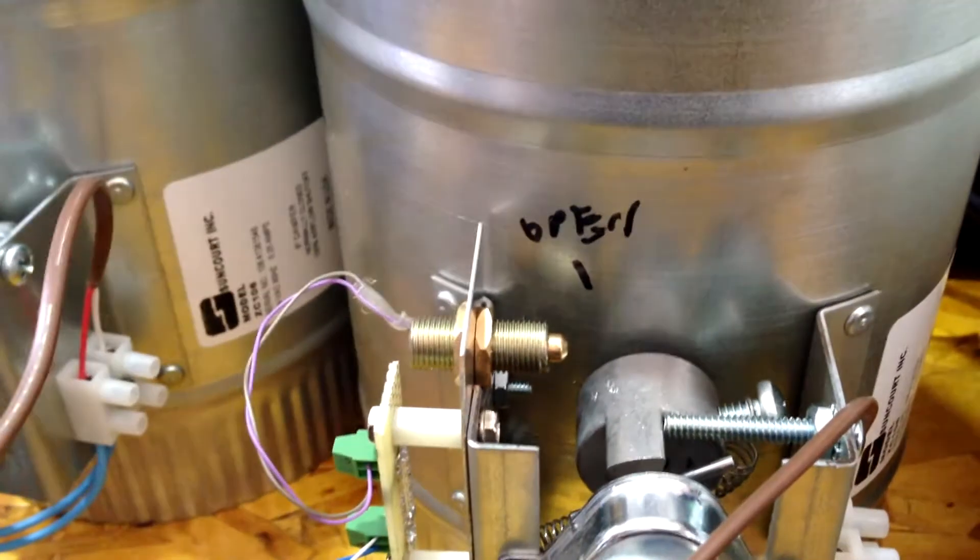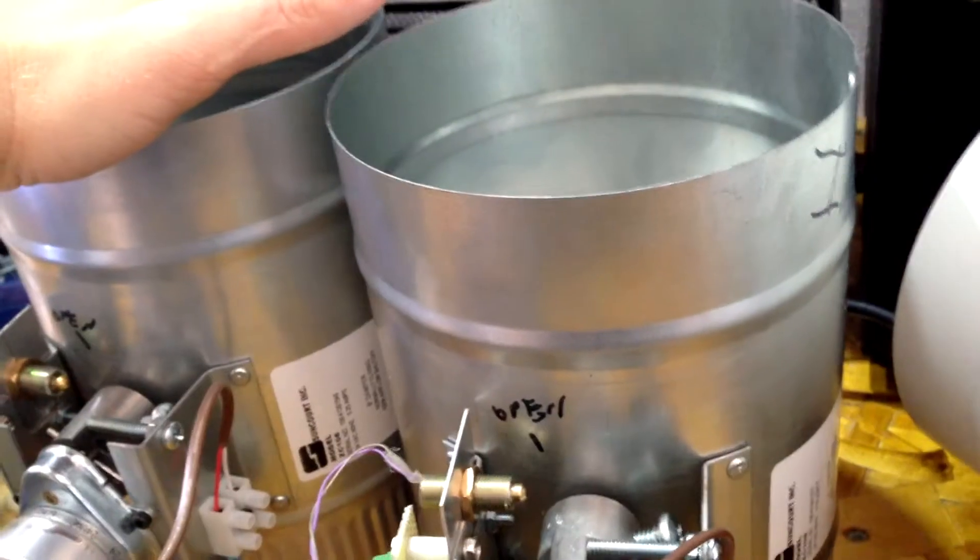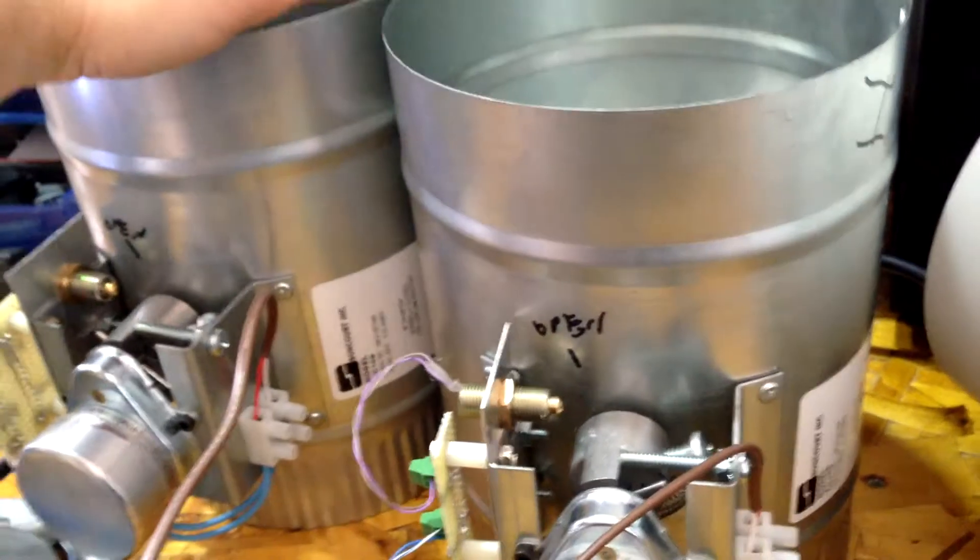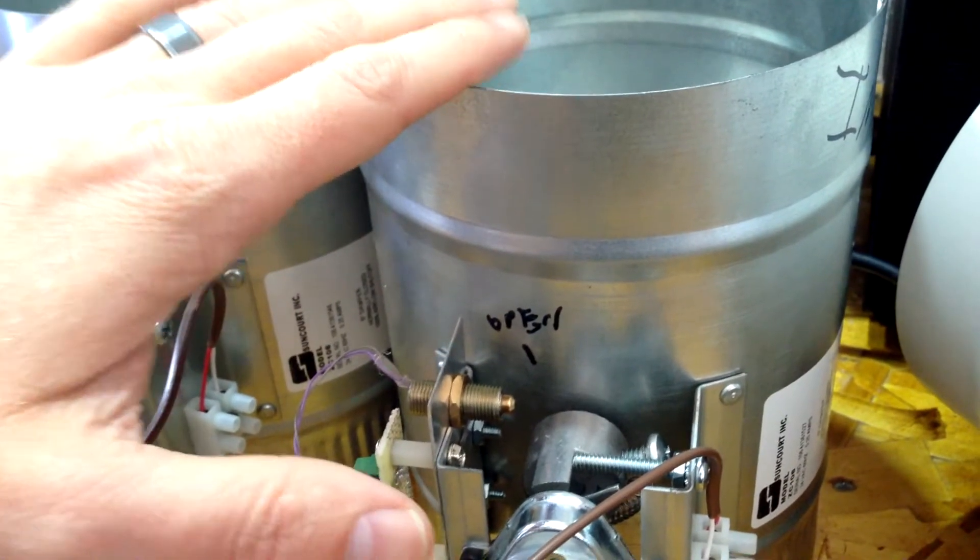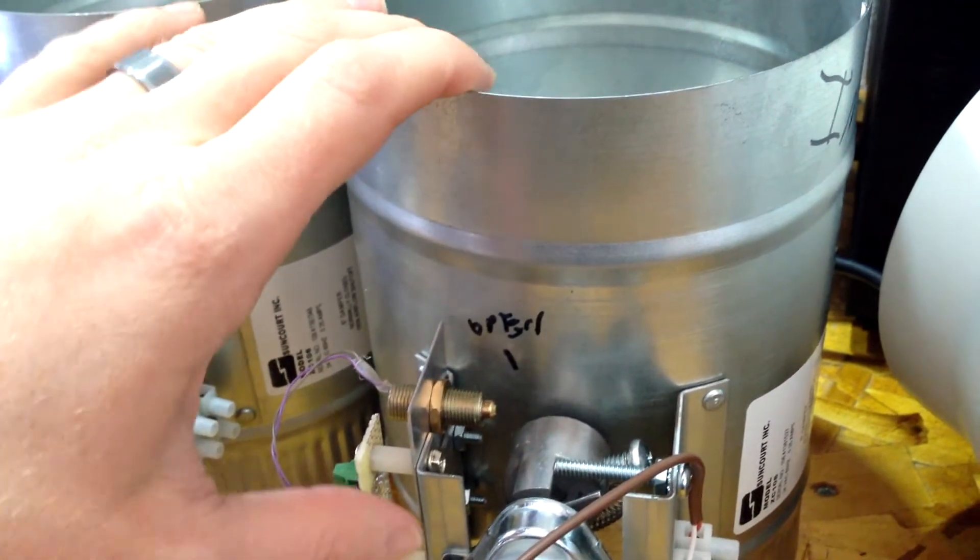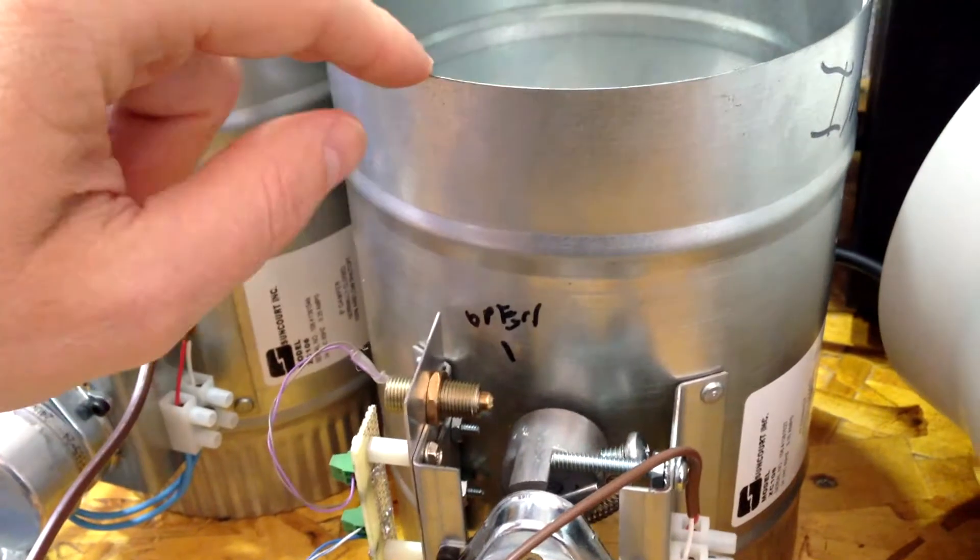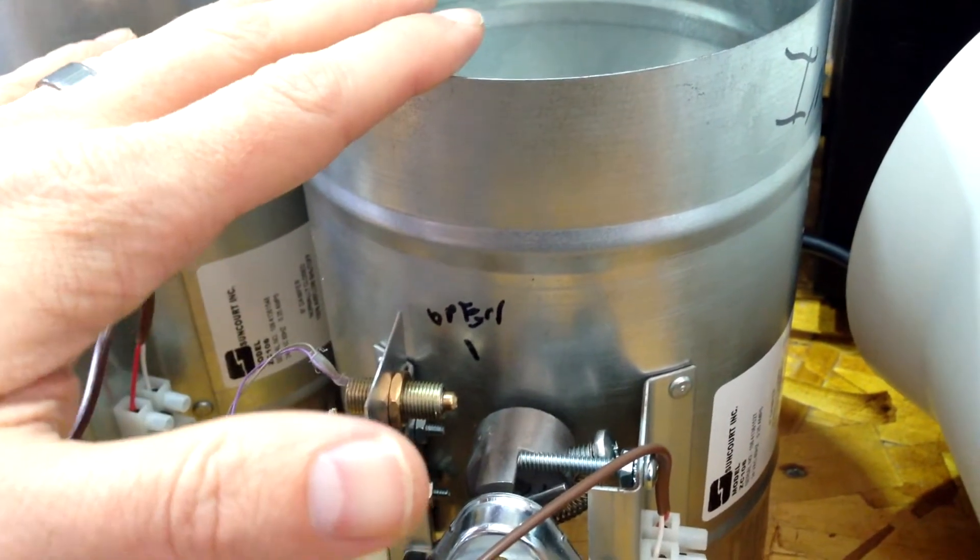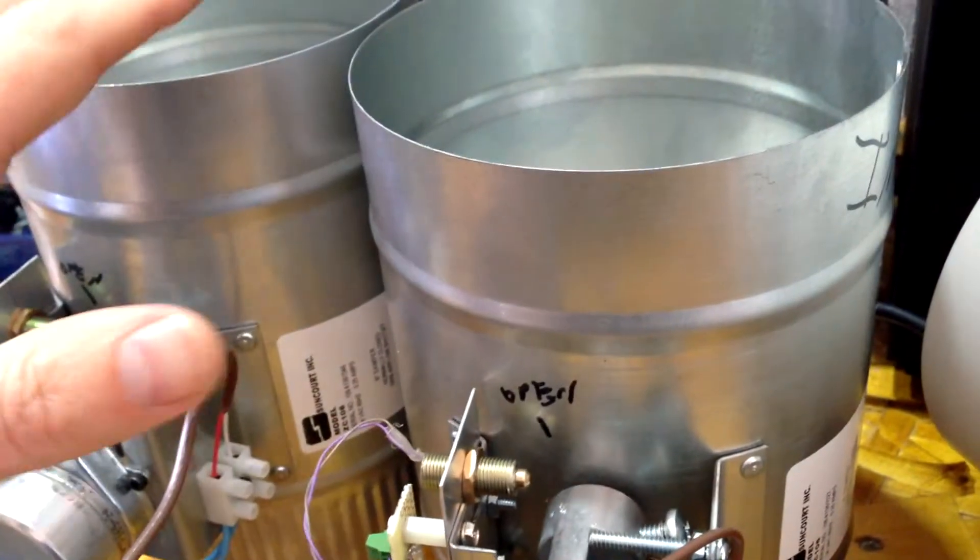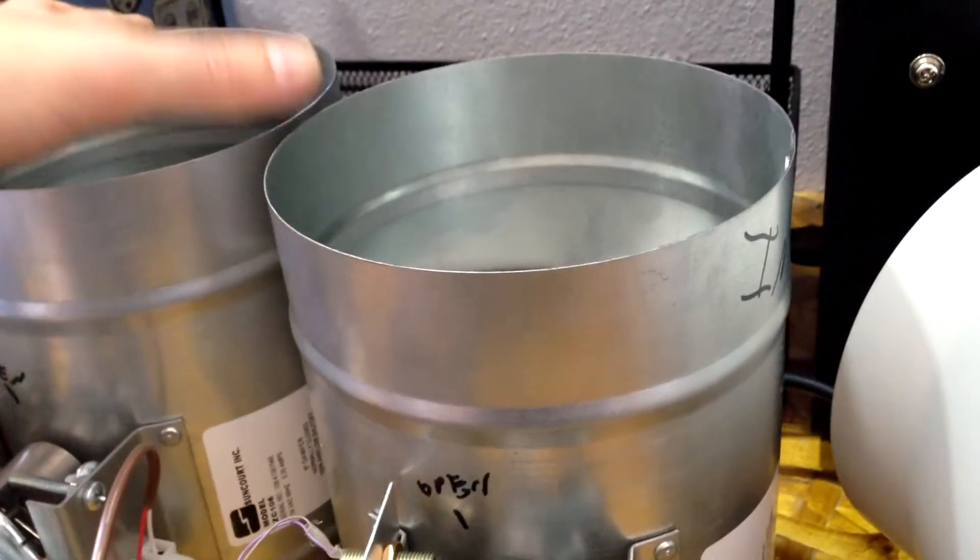Okay, so a couple changes. Before, when I would open the needed damper, one of the dampers opened, then I would simply set that relay high, or that output high, to activate the relay, to open the damper, wait the 30 or 35 seconds that it takes for the damper to open, and then close the other one if necessary, or wait that and then turn the fan on so that we always had a damper open before the fan was turned on.